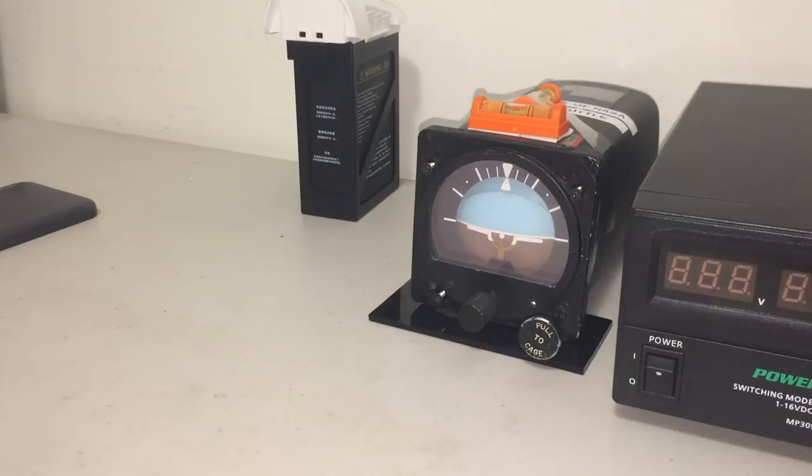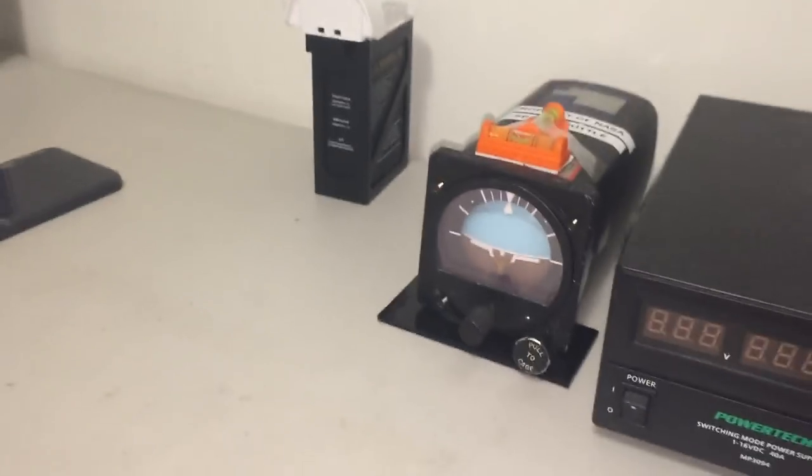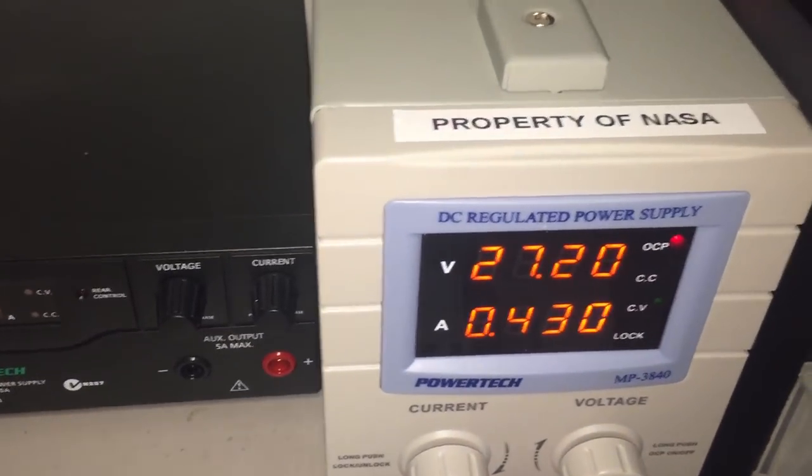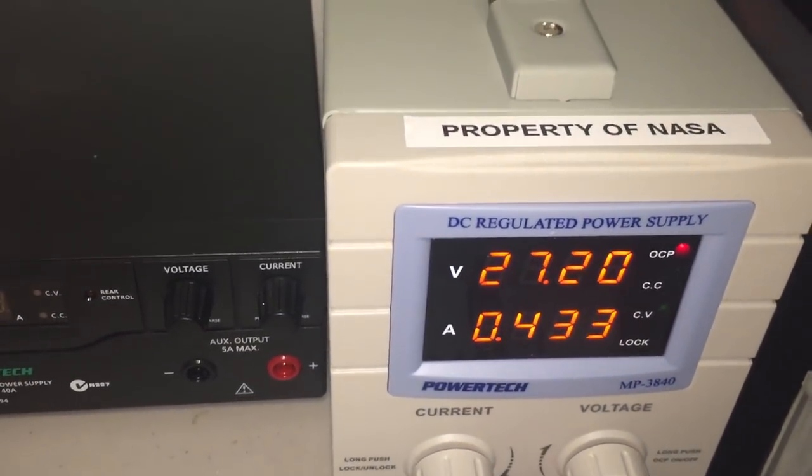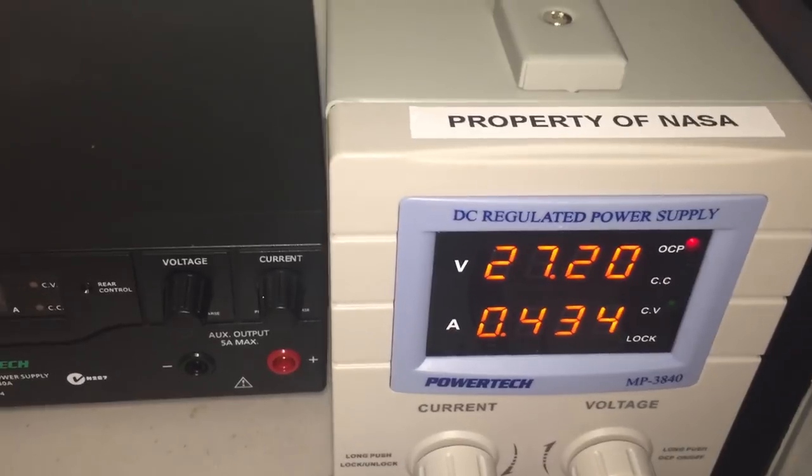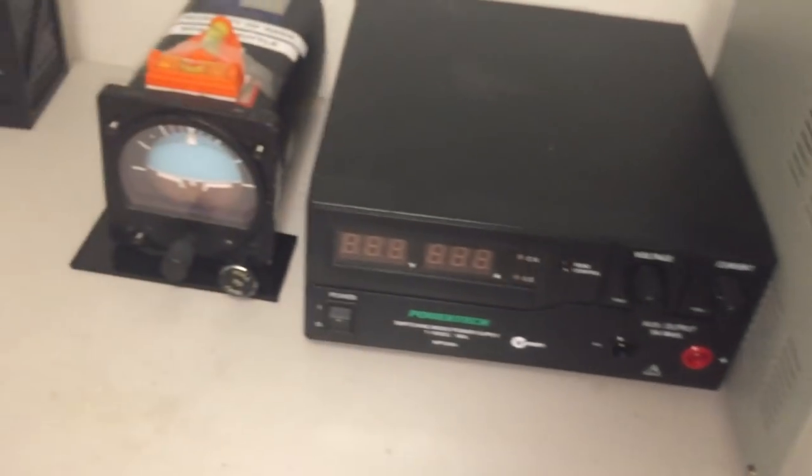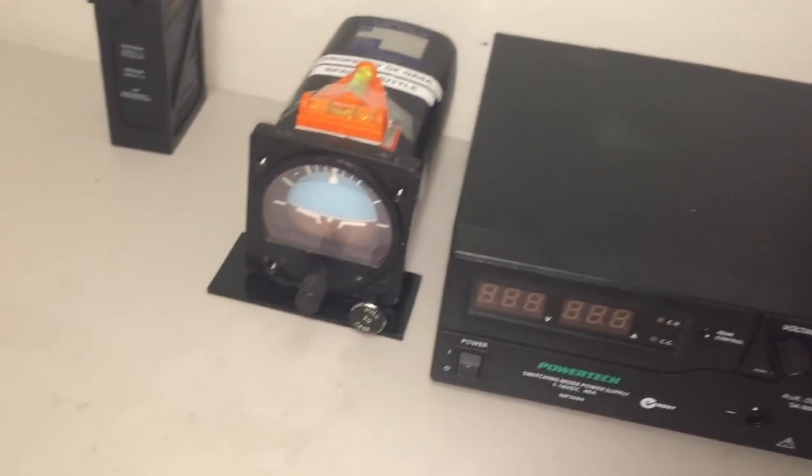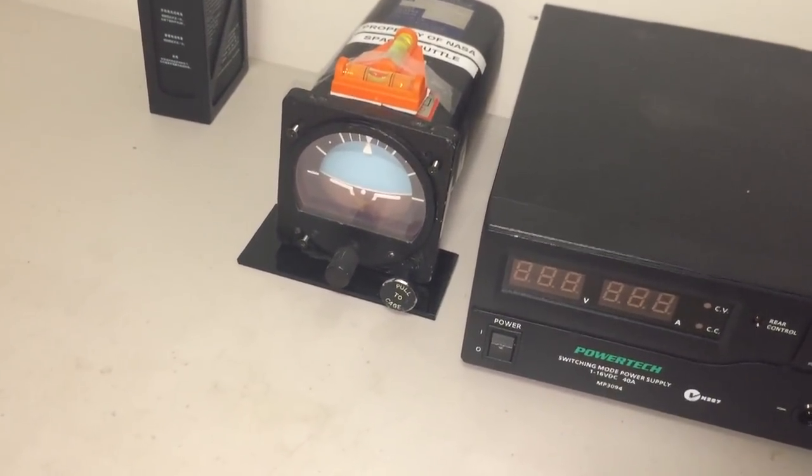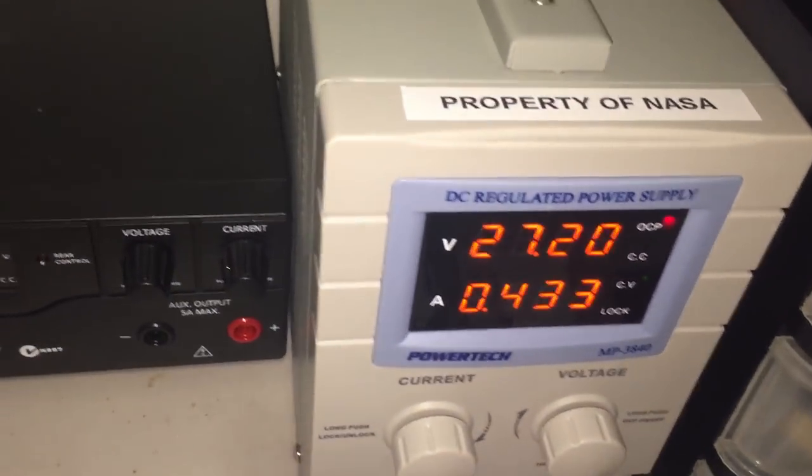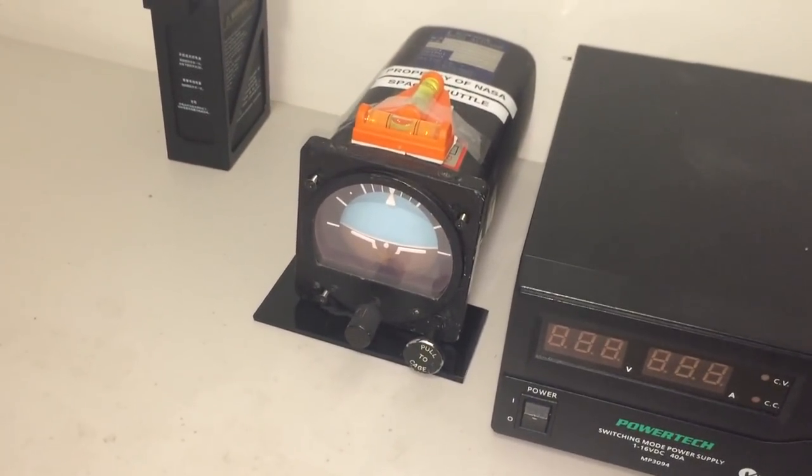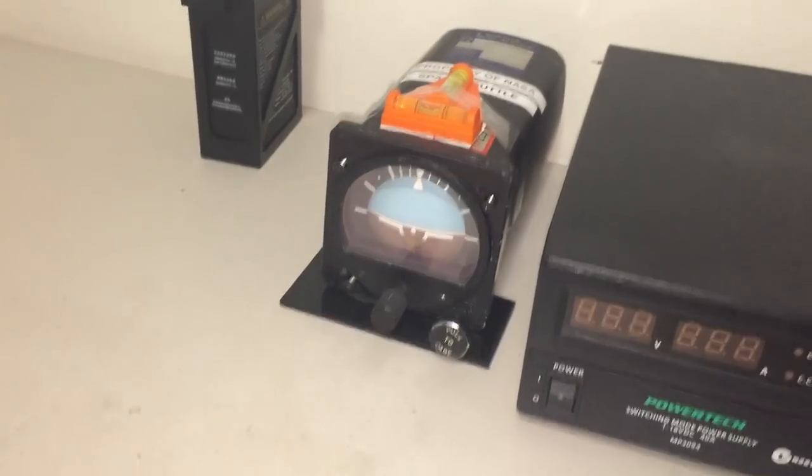I have tried it already. It takes about 35 to 40 minutes. So the gyro is being powered at 27.2 volts. From the operating manual, it states a minimum of 26.5 volts to operate correctly. So we've got sufficient power. It's operating within correct parameters.